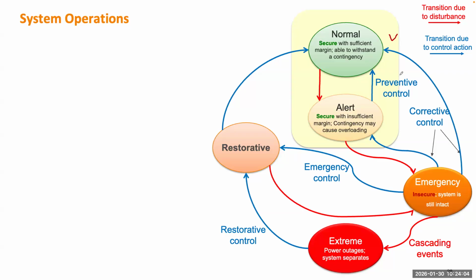But in some cases, the system right now doesn't violate any standard, but you can predict that if the next contingency happens, some equipment will have violations, like voltage becoming lower or higher than the limit, or some line being overloaded, but that has not happened yet. For the next contingency, very likely the system will become insecure. So that is considered the alert state. The alert state is basically still normal, but it doesn't have enough safety margin for the system to withstand a next contingency. For example, right now it's in the N-1 condition with no violation, but if you add another contingency, N-1 minus 1, then the system will become insecure. So the system is secure in terms of N-1, but not secure in terms of N-2 or N-3 or more.